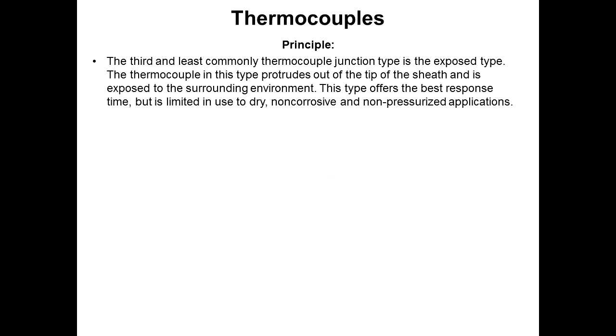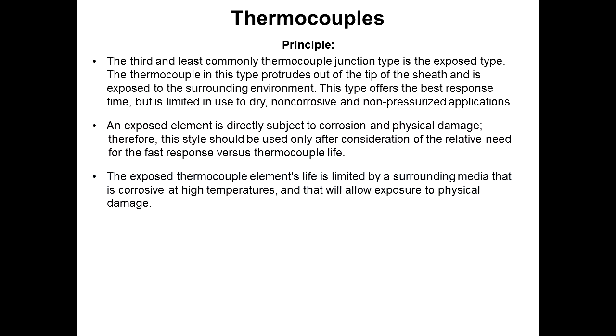The third and least common type is the exposed type. This is where the wires actually protrude out the end of the sheath and they're exposed to the surrounding environment. These are very good for limited applications: dry, non-corrosive, non-pressurized applications. They're much faster than the others, which are enclosed in a sheath.